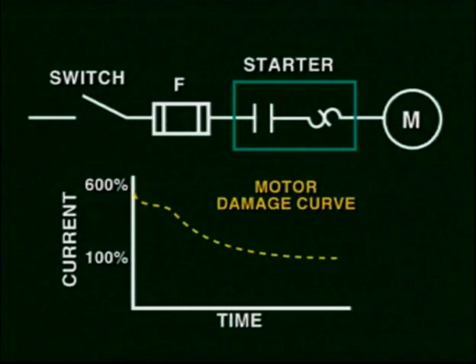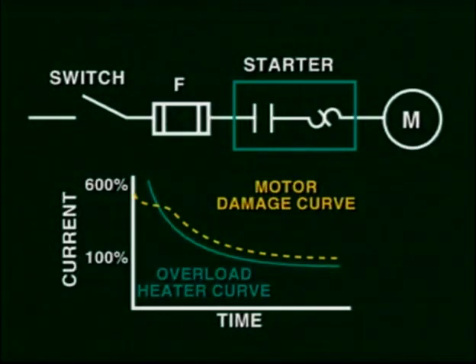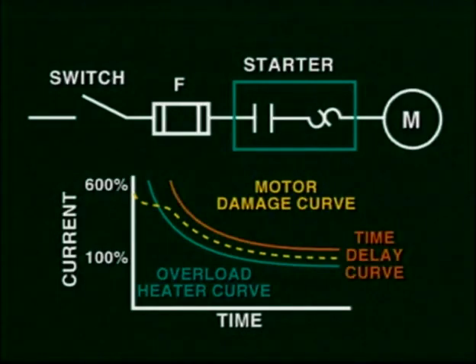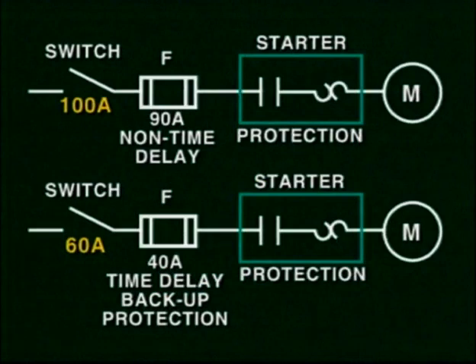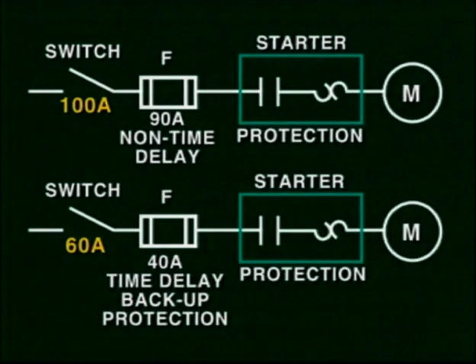This graph illustrates the motor damage curve and the protecting curve provided by the motor overload heaters. The dual-element curve is shown as backup protection. Additionally, the switch used in the dual-element circuit will be of smaller current carrying capacity than the one in the 90-amp circuit, therefore reducing space and money. Remember, a switch rating must be equal to or larger than the amperage rating of the fuse protecting the circuit.